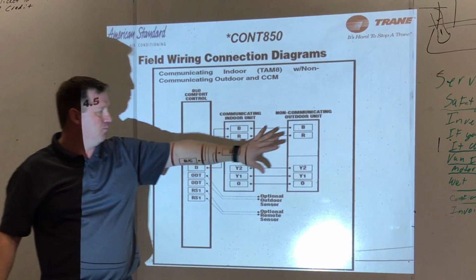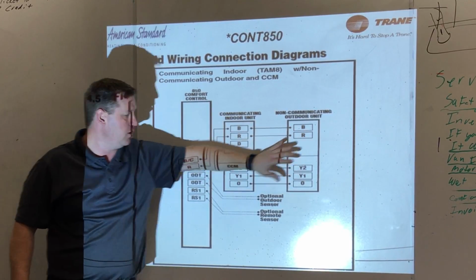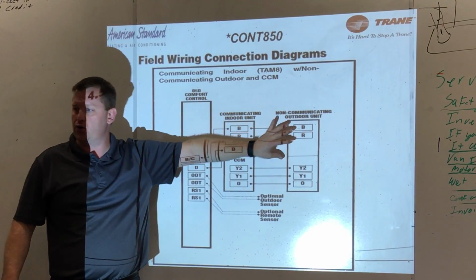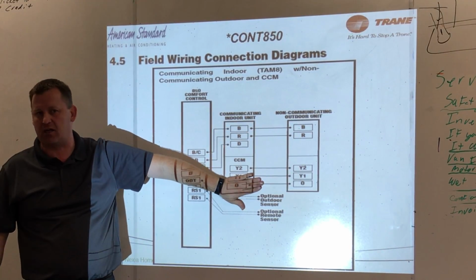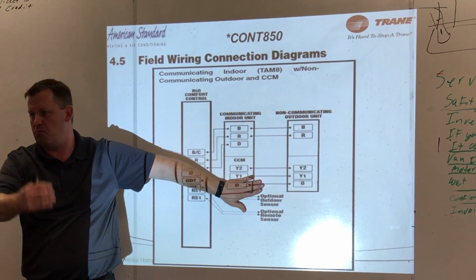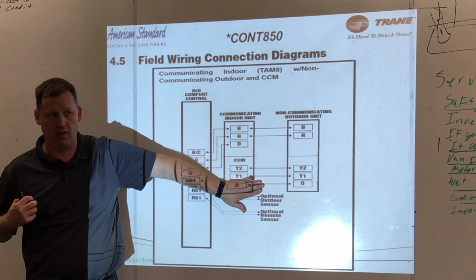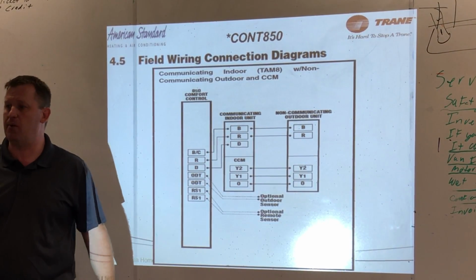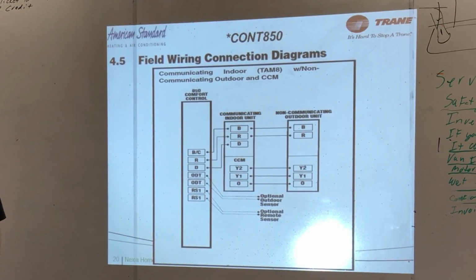So whenever you guys pull off a non-communicating outdoor unit and go to a communicating outdoor unit, you've got to disconnect the compressor control module. Remove it from the TAM8. Okay? Because that was a problem a while back, and that created all sorts of headaches.